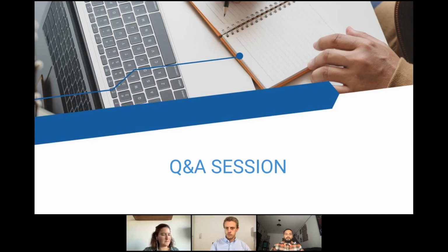Okay, so we had another question. How often do I need to update the clinical evaluation? So according to Section 61, you need to update it through its entire product life cycle.